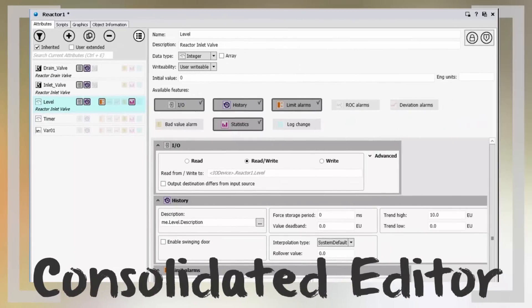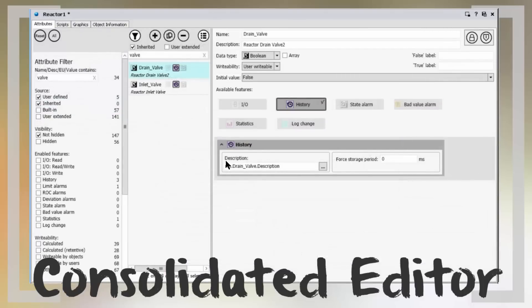The Attribute Editor has been designed from the ground up with engineering efficiency in mind. Creating attributes is faster than ever before. As you create new attributes, it even remembers the last set of parameters used, so configuration of additional attributes is as easy as just enabling those same features. Duplication of individual or multiple attributes in one operation is also available. Advanced filtering capabilities are also available to search throughout the object — for example, for any reference of the word 'valve' in any of the parameters within the object, including scripts. You can also change filtering settings to narrow down display criteria, for example to see only those attributes that are alarmed or historized.